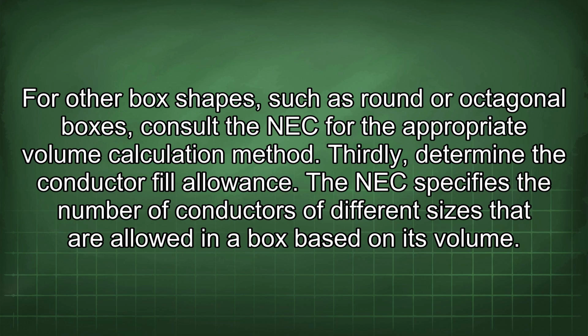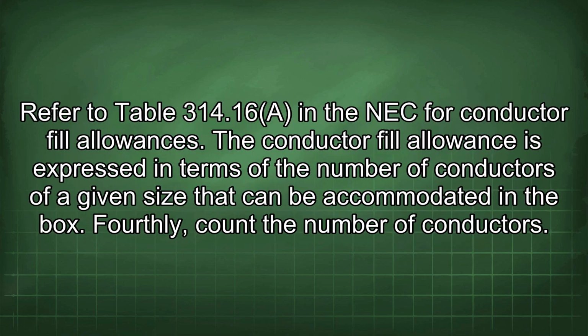Thirdly, determine the conductor fill allowance. The NEC specifies the number of conductors of different sizes that are allowed in a box based on its volume. Refer to Table 314.16 in the NEC for conductor fill allowances. The conductor fill allowance is expressed in terms of the number of conductors of a given size that can be accommodated in the box.